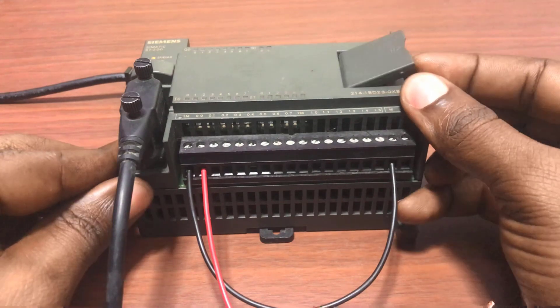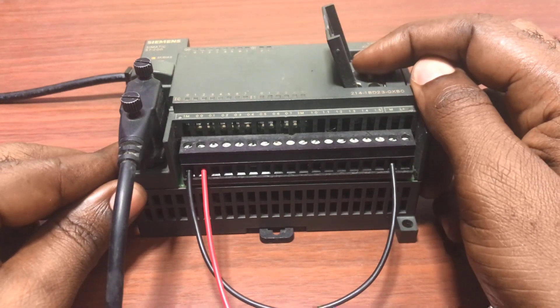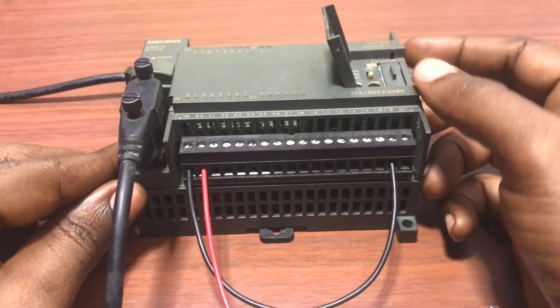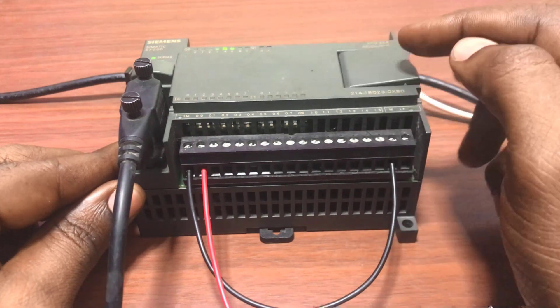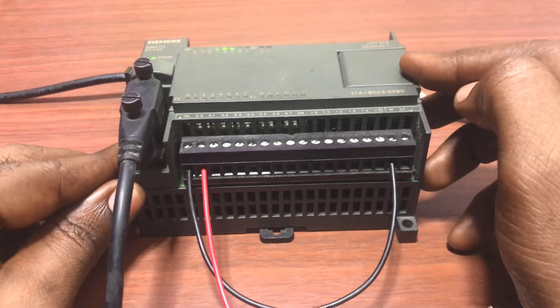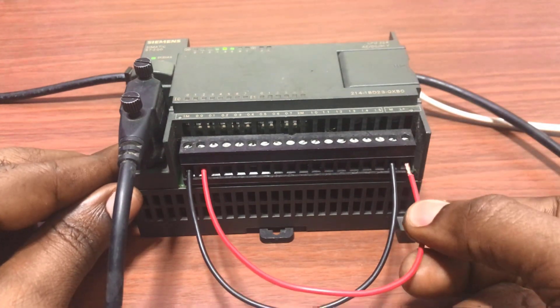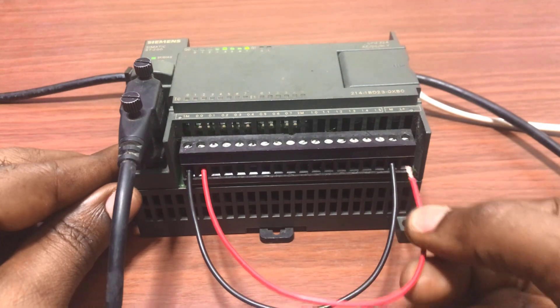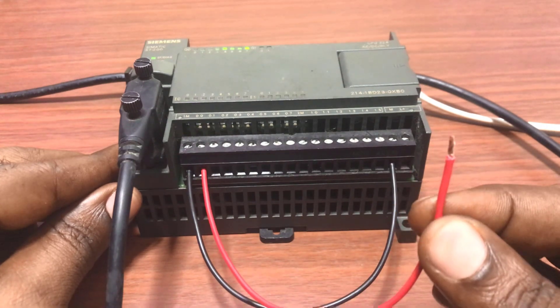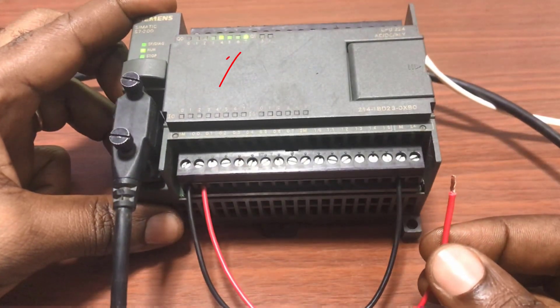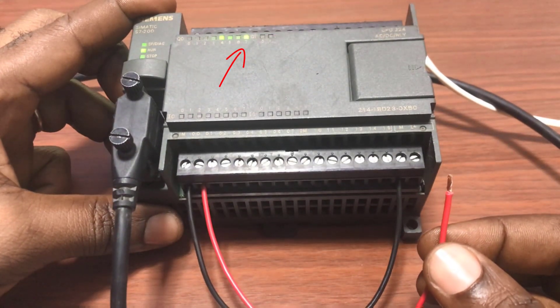And now let's test it. I now need to bring the switch to stop mode and then back to run mode again. PLC is in run mode. I sent 24 volts to the input. We can see that the output is on. And then it's latched. Working perfectly.